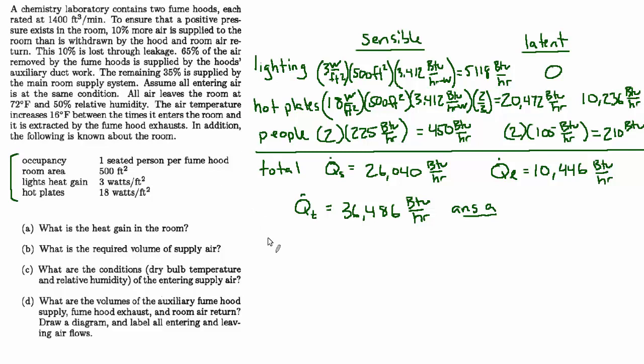So we'll just use our usual rule of thumb: Q̇_sensible = 1.08 × CFM × ΔT. And if we solve that for the volume, CFM = 26,000 divided by 1.08. And the ΔT—they said the air temperature increases 16 degrees between when it enters the room and when it's extracted—so that is the ΔT.